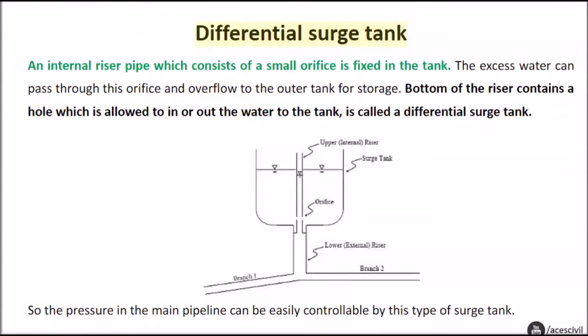Differential surge tank: An internal riser pipe which consists of a small orifice is fixed in the tank. The excess water can pass through this orifice and overflow to the outer tank for storage. The bottom of the riser contains a hole which allows water in or out of the tank. The pressure in the main pipeline can be easily controlled by this type of surge tank.